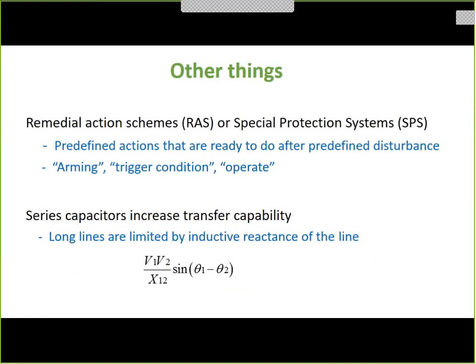Remedial action schemes, RAS schemes, also known as special protection systems. These are things that you could do, but you're not going to do them unless you really need it. So they are predefined disturbances and your reaction to that disturbance. And it involves arming the device. It's like pulling the trigger back, but you don't pull the trigger. You have a trigger condition. Something bad happens. Then you actually operate the control scheme.